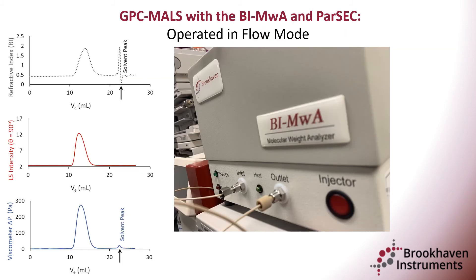Multiple types of detectors can be coupled with a GPC system. In addition to MALS, common detector types include RI and viscosity detectors. Note that RI and UV detection are proportional only to concentration, whereas viscosity will be sensitive to both the concentration of solute but also to hydrodynamic parameters such as shape. UV is often inadequate to detect synthetic polymers which, in contrast to protein samples, often have minimal UV absorbance.